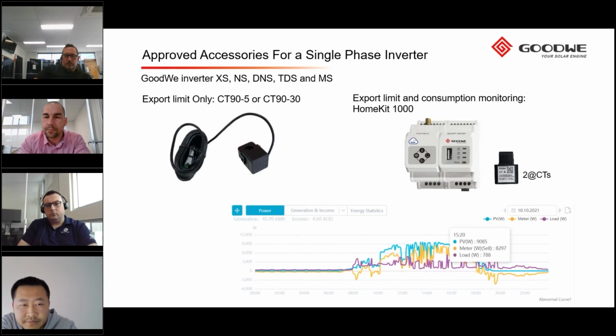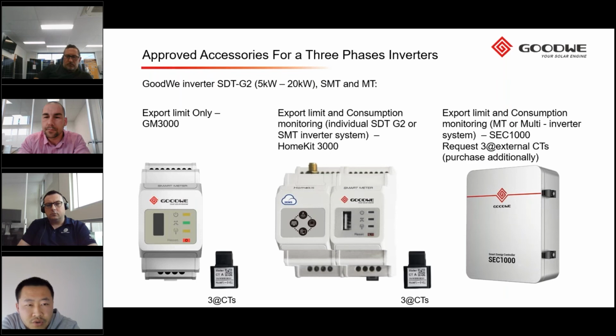For three phase, could we just move to the next slide? Yeah, for three phase we currently have the SDT G2, which is from 5 kilowatt to 20 kilowatt three phase, or the SMT from 25 to 36, and the MT 50, 60, and 80 kilowatt inverters. Similar to single phase, if the customer just wants to do export limit, they just need to purchase this GM3000 meter, which comes with 3 CT clamps already pre-connected to the meter. This only does export limit.